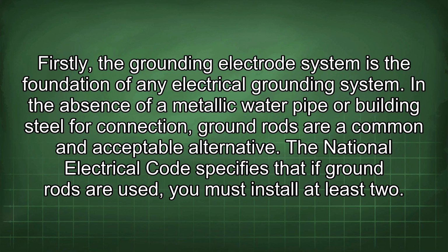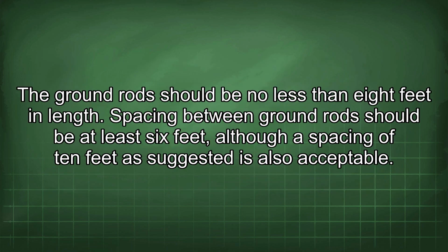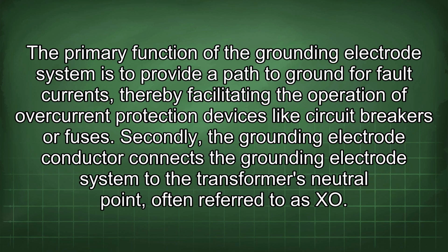Firstly, the grounding electrode system is the foundation of any electrical grounding system. In the absence of a metallic water pipe or building steel for connection, ground rods are a common and acceptable alternative. The National Electrical Code specifies that if ground rods are used, you must install at least two. The ground rod should be no less than 8 feet in length. Spacing between ground rods should be at least 6 feet, although a spacing of 10 feet as suggested is also acceptable. The primary function of the grounding electrode system is to provide a path to ground for fault currents, thereby facilitating the operation of overcurrent protection devices like circuit breakers or fuses.